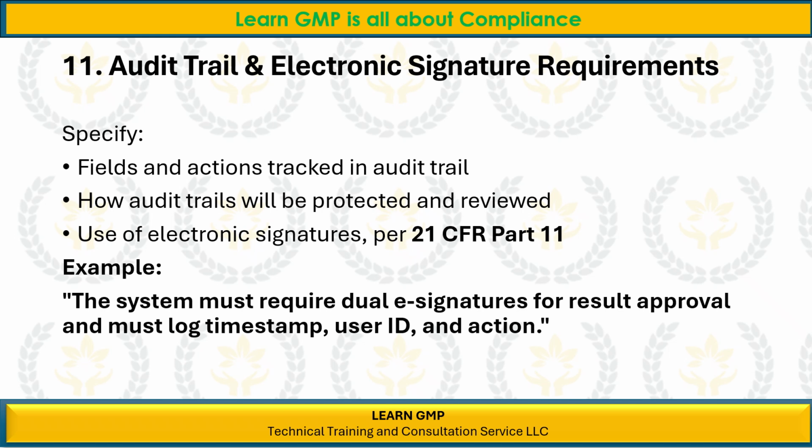Audit trail and electronic signature requirements. Specify fields and actions tracked in audit trail. How audit trails will be protected and reviewed. Use of electronic signatures, per 21 CFR Part 11. Example. The system must require dual e-signatures for result approval and must log timestamp, user ID, and action.